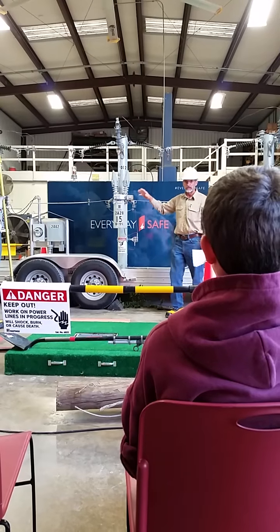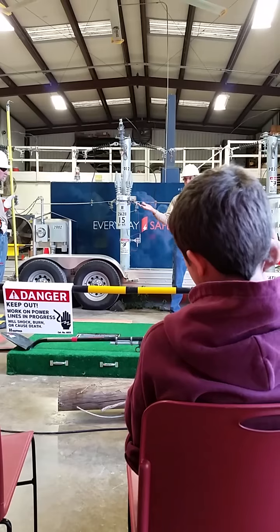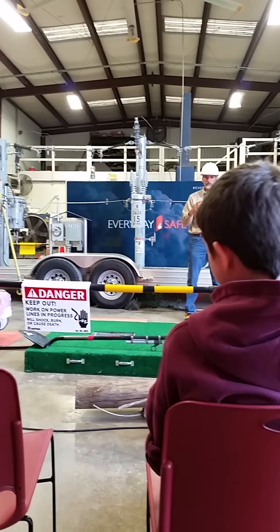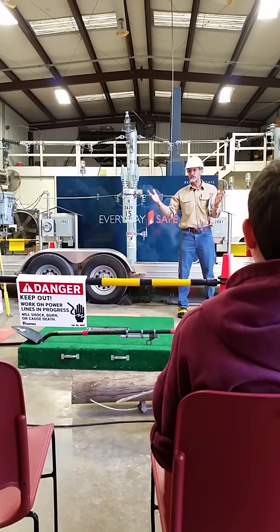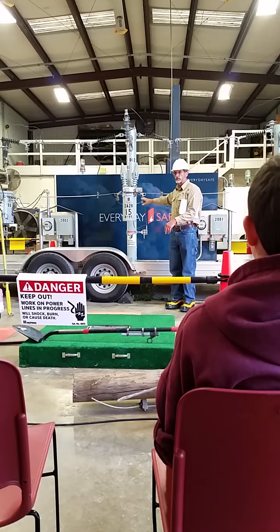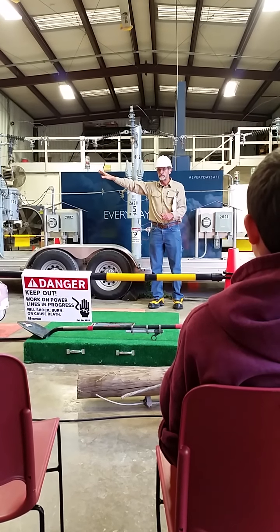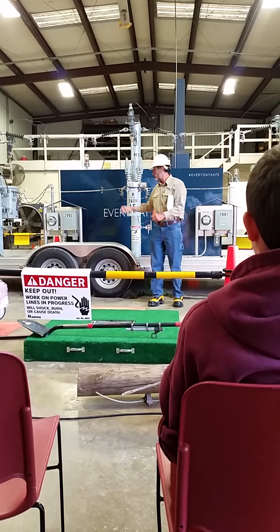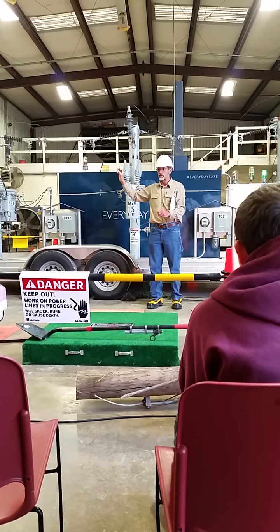Now, I'll go ahead and explain this while I'm talking about the breaker. Have you ever been at home and your lights go off, come back on, go off, come back on? You know what's happening? All right, something's happened out there on that line. Let's say this is an OCR, an oil circuit recloser. Let's say something's happened down the line, maybe a car wreck, maybe a squirrel. All this recloser knows is something's wrong down there. Too many amps are going through here.